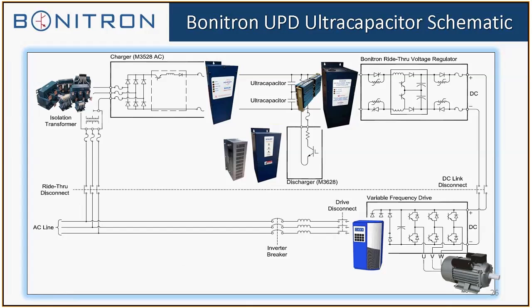Here is the short-term outage ride-through block diagram. We come from the AC line through the disconnect, which once again disconnects the full system, energy storage, everything, from the variable frequency drive. This is very important for maintenance, and for having to get into the cabinet when you want to lock out, tag out the drive and the ride-through system to be able to work on it.